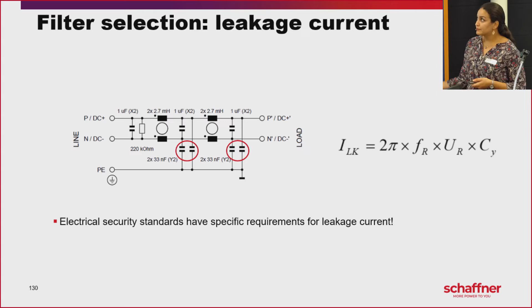Another criterion that is important when it comes to filter selection is the leakage current. The leakage current is actually what we face. I don't know if you have faced this or heard of it, but whenever we install a filtered equipment or an external filter in an installation, we get a claim about the differential circuit breaker that it trips. And usually this is due to the common mode capacitors, because filters, this is a typical scheme of a filter, help us filter a high frequency signal, but through the common mode capacitors that we have between each line and earth, we generate a leakage current that is, at the end of the day, proportional to the common mode capacitor.